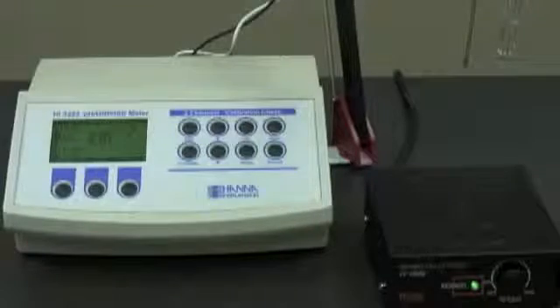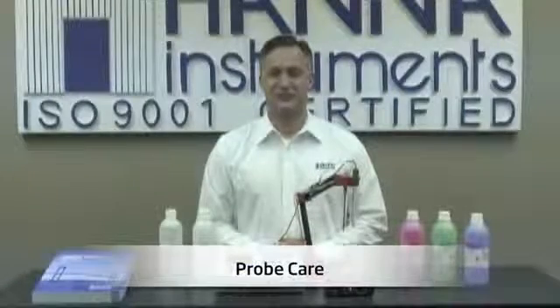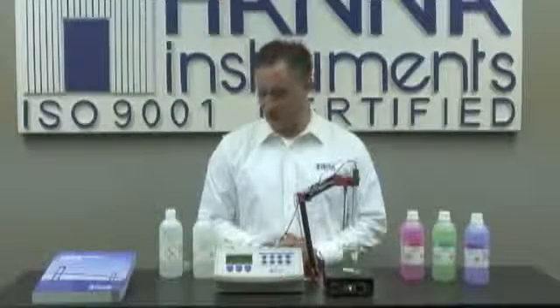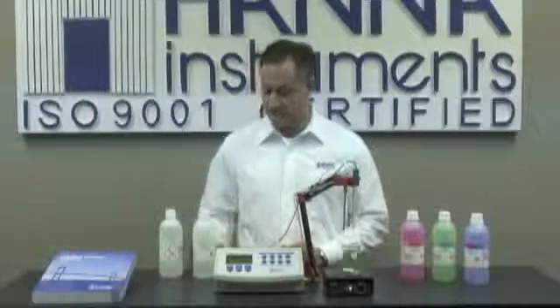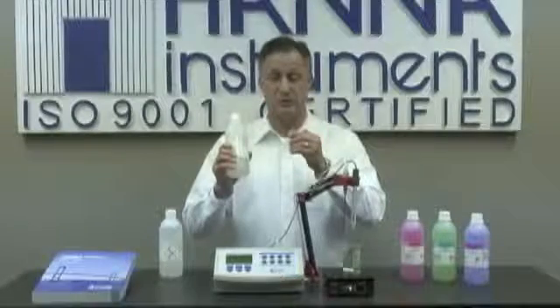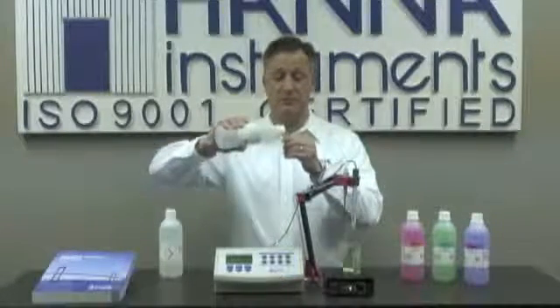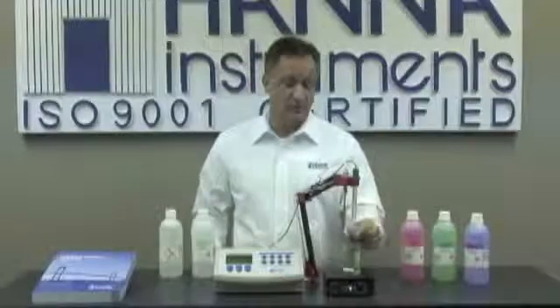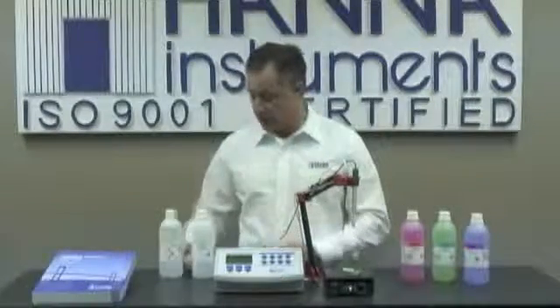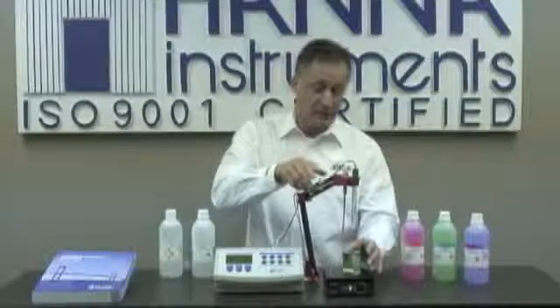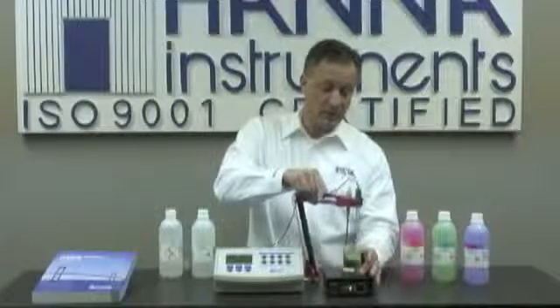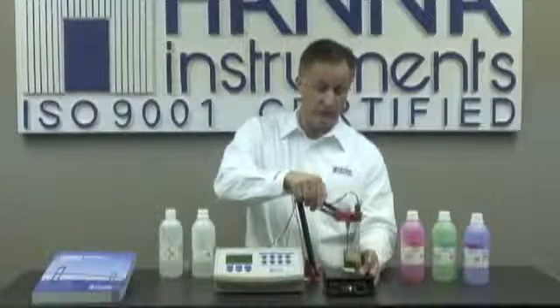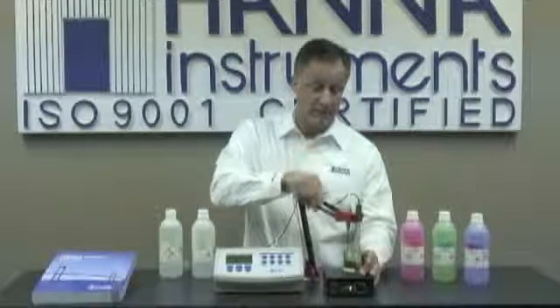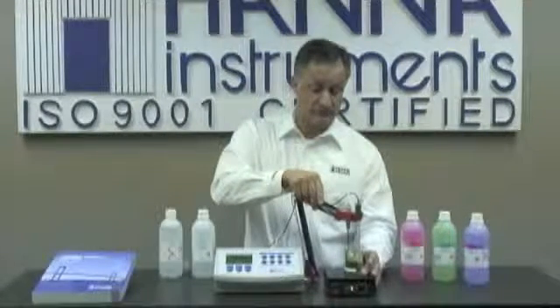Next, we are ready to take our measurement. Some final notes. It's extremely important to keep your probe conditioned after usage. In that case, I recommend using a storage solution, HI 70300. If you choose to store in the probe's protective cap, simply pour some storage solution in the cap and put it on the probe accordingly. If you don't have storage solution, again, it's okay to keep the probe in a buffer. Preference is 4. If you don't have 4, 7 is okay as well. Never keep the probe in deionized water.